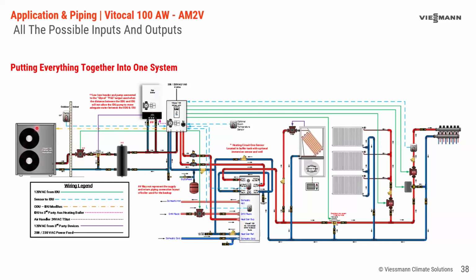And all of our drawings show they're pretty close, because this is going to be pulling heat or rejecting heat, and the outdoor temperature sensor is going to see maybe a blend of that temperature. So just like you wouldn't put the outdoor sensor near the exhaust on a boiler, you don't want to put it too close to the heat pump as well.